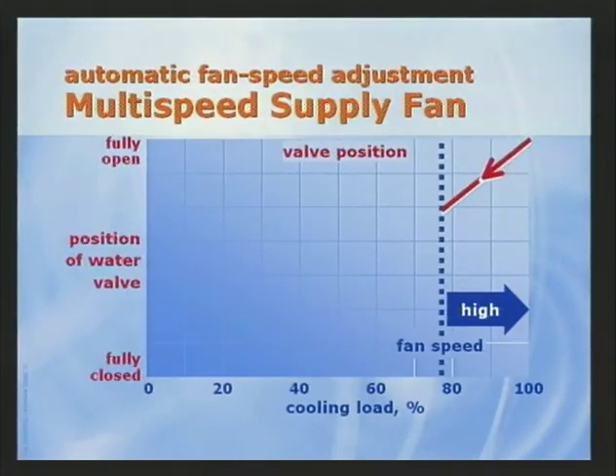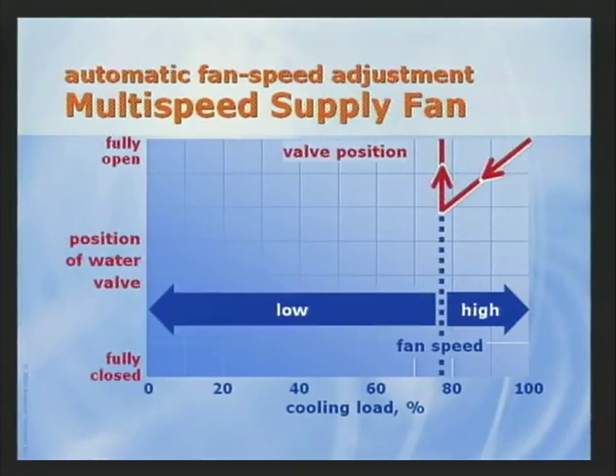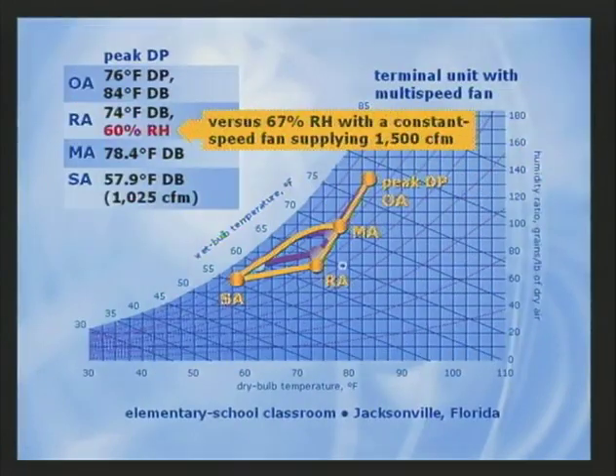As the cooling load decreases further, the terminal unit controller automatically responds by switching the fan to low speed, and the control valve opens to compensate. As the load continues to decrease, the valve reduces water flow through the coil while the supply fan continues to operate at low speed. This reduced supply airflow results in a colder supply air temperature at part load. The coil removes more moisture and dehumidification performance is improved. In this example, space relative humidity improves from 67% to 60%.